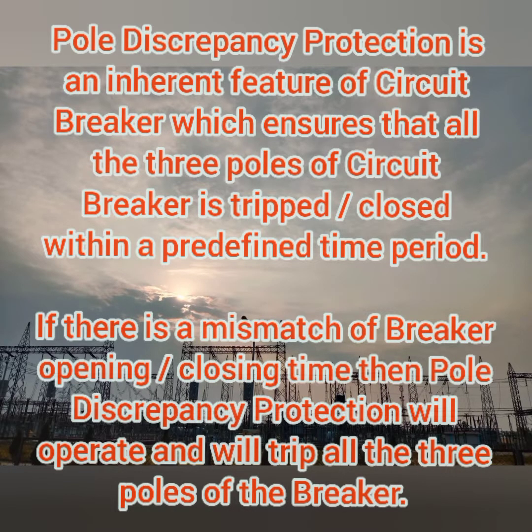Hello everyone, welcome to my channel. I'm Vignesh Anand. In this video we are going to see about the pole discrepancy in your circuit breaker. Pole discrepancy protection is an inherent feature of a circuit breaker which ensures that all three poles of a circuit breaker are tripped or closed within a predefined time period. If there is any mismatch in breaker open or closing time, the pole discrepancy protection will operate and trip all three poles.